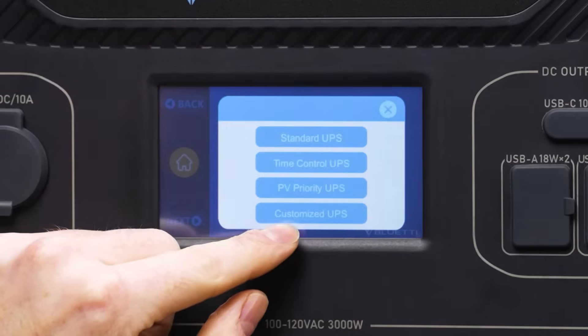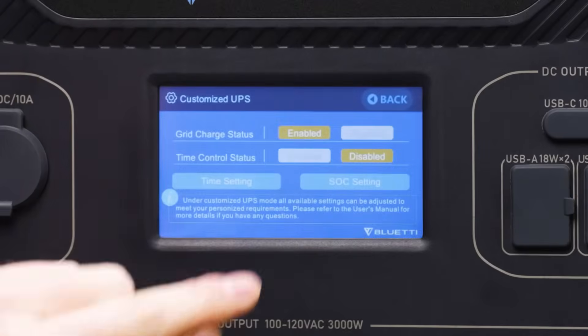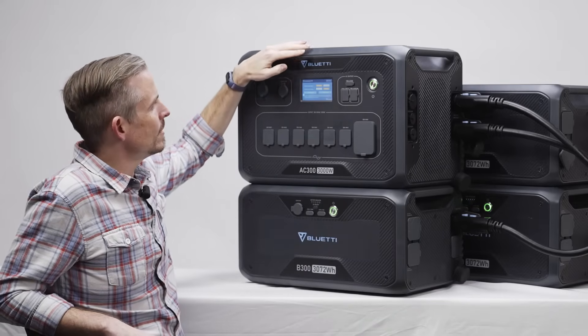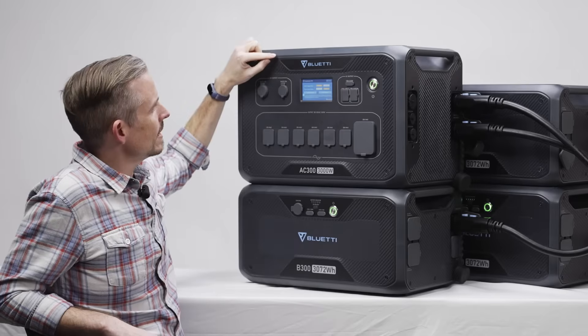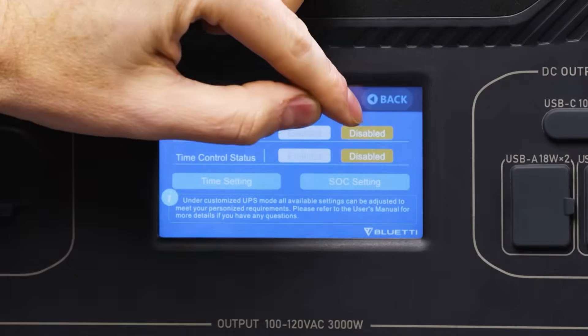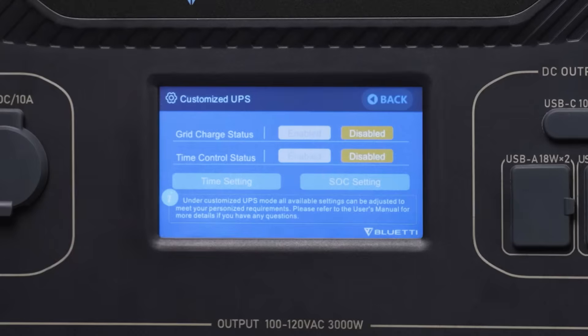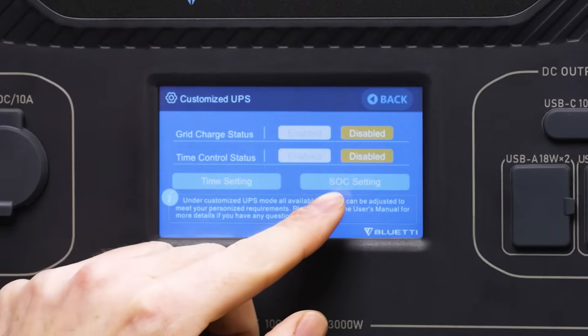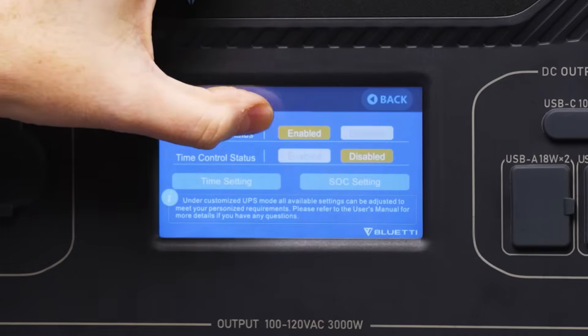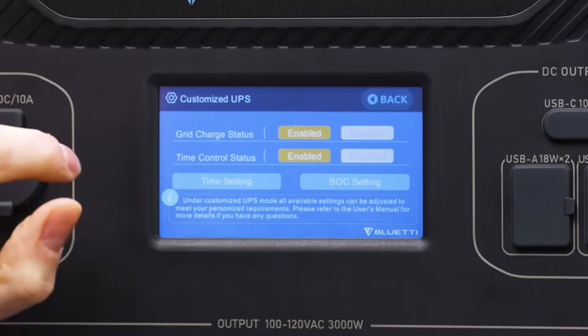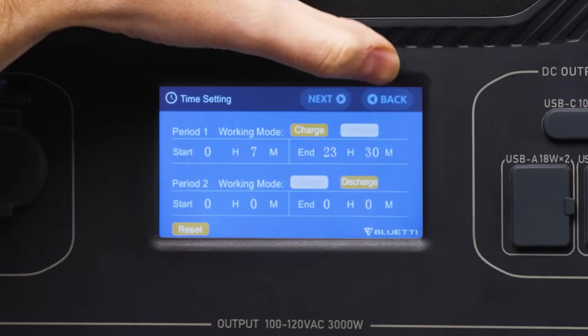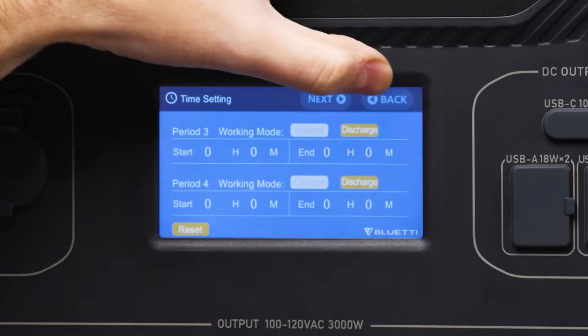Finally, we have customized UPS. This is something of a master control for all of the other UPS settings. If you have grid charge disabled or time control disabled, this overrules all of the other settings in time setting or SOC setting. So if you want to use those settings, please be sure to enable them here. After that, you can set your time or parameter as shown before.